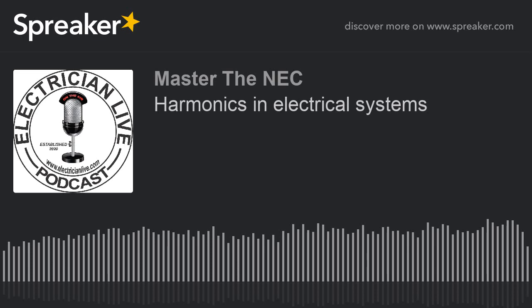Well, hey, everybody. Welcome to the show, and hopefully you're excited about what we're going to talk about today, because we're going to talk a little bit about harmonics. We're not going to get too awful complicated because it is a podcast, but we're going to talk a little bit about how it can affect a system, and answer some of those questions people have about neutrals and why, when we have a 4-wire 3-phase Y system, the neutral has to be counted as a current carrying conductor, and all of those things that seem to confuse people. But yet you don't count the neutral in a single phase application where it only carries the unbalanced load between phase A and phase B.